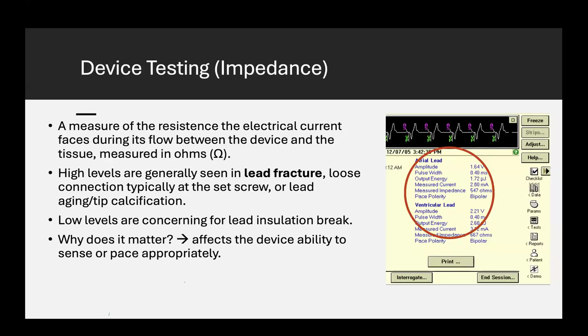On the other hand, low levels are concerning for lead insulation break, and both problems would affect the device's ability to sense or pace appropriately, and this can be an urgent need to reposition or replace the lead, especially in patients who are pacing dependent. And it might require a temporary pacing insertion or applying transcutaneous pads if the procedure can be done safely and soon enough to save the patient, putting another line in the heart.